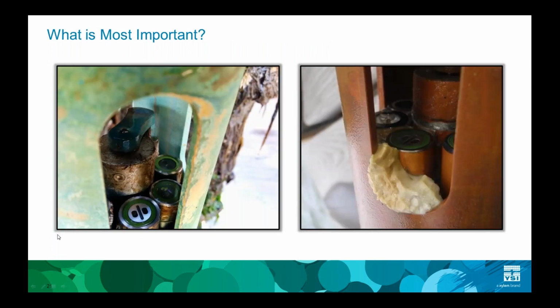What's most important to see here, however, is not the accumulation of fouling on the sonde itself, but rather how the sensors and data are affected. These photos demonstrate the power of the EXO central wiper in maintaining the most critical aspect of an EXO-2, the sensor head where the measurements are taking place.